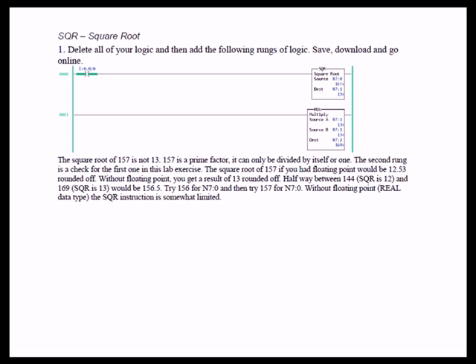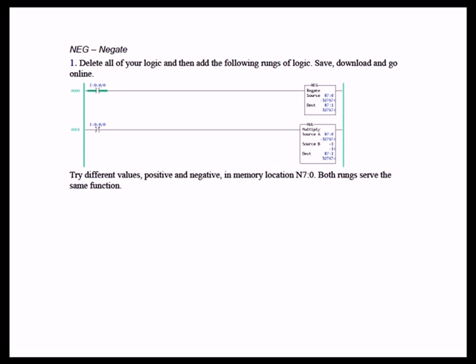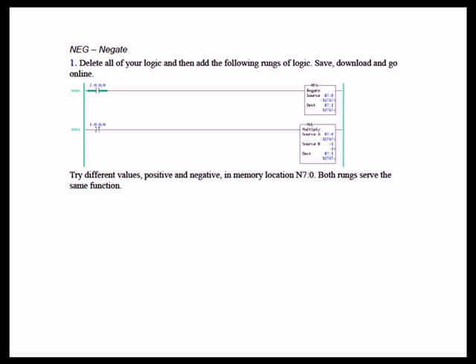The long and short of the negate instruction is that when it is executed on a true condition of the rung, it is exactly the same process as multiplying by a negative 1. We demonstrate this by using two rungs in the lab. One uses the negate instruction. The other multiplies the source by a value of negative 1. The results are the same.